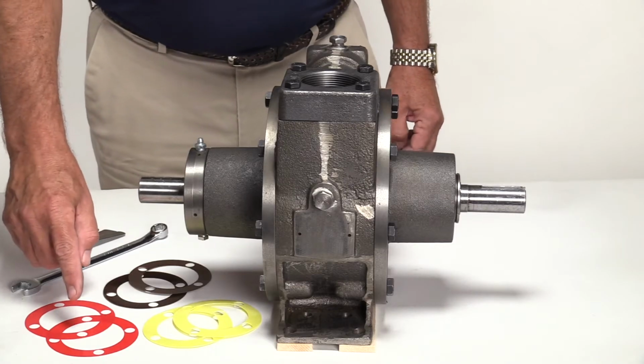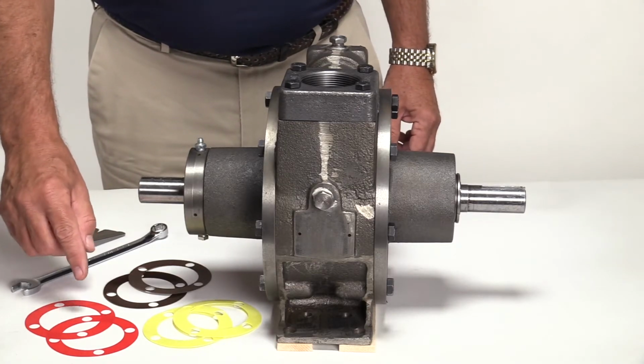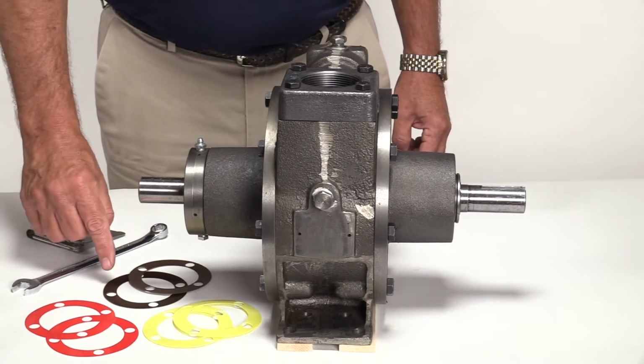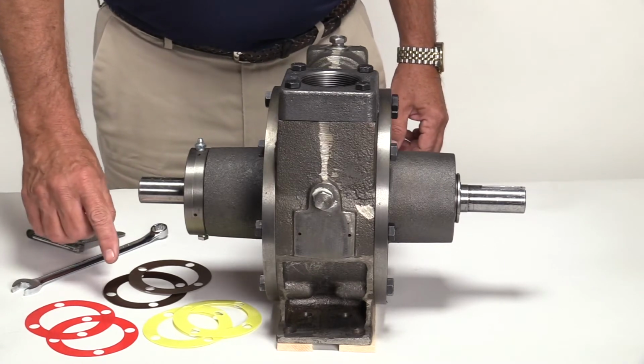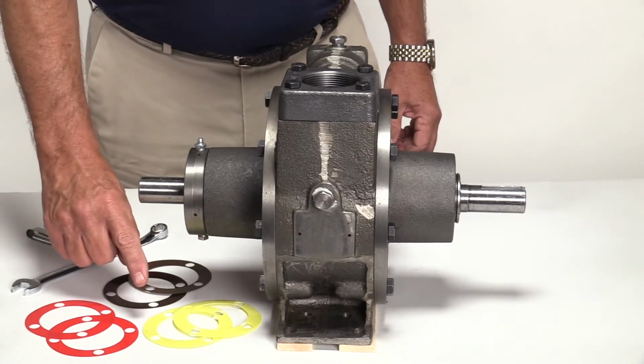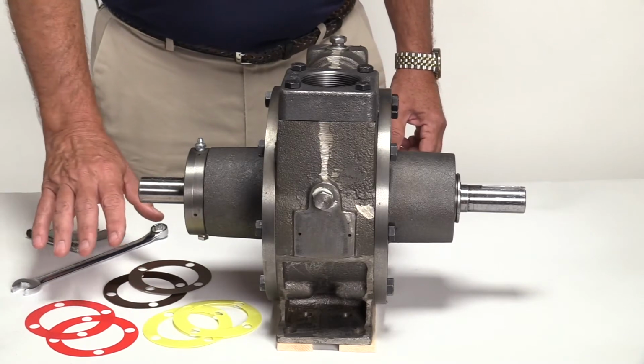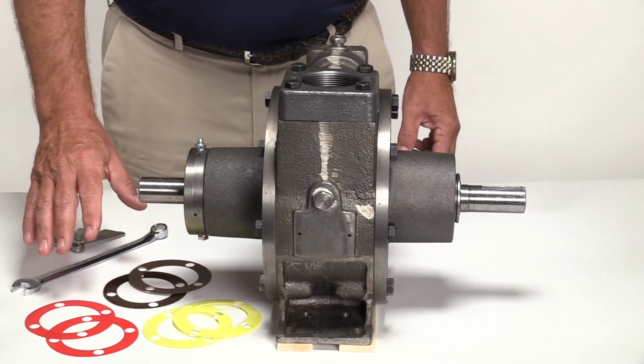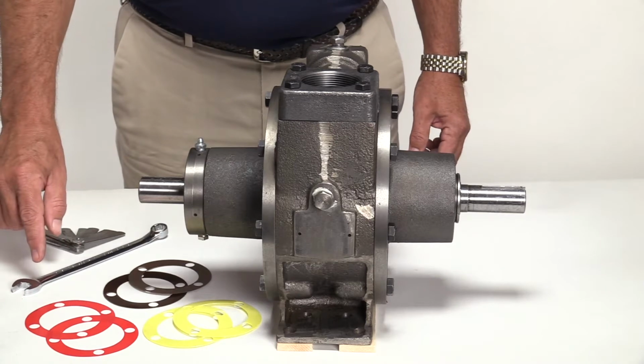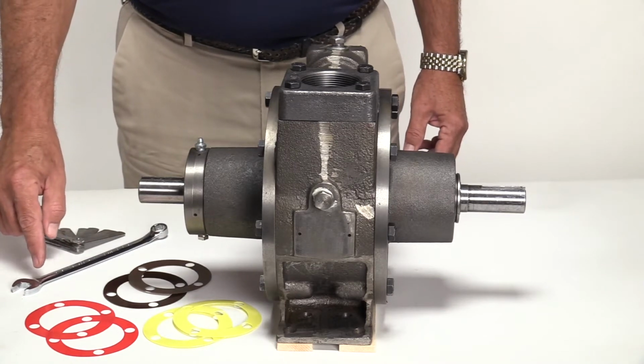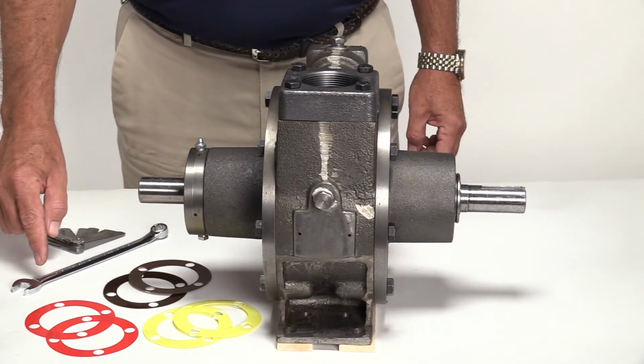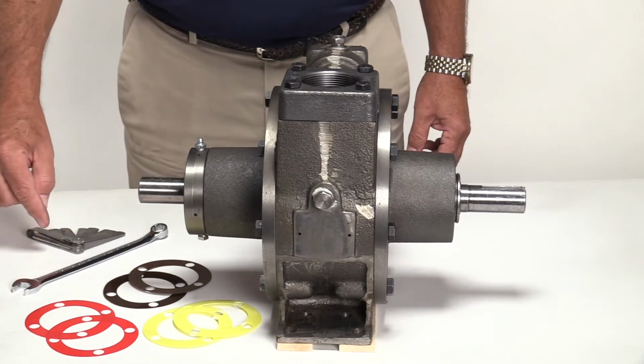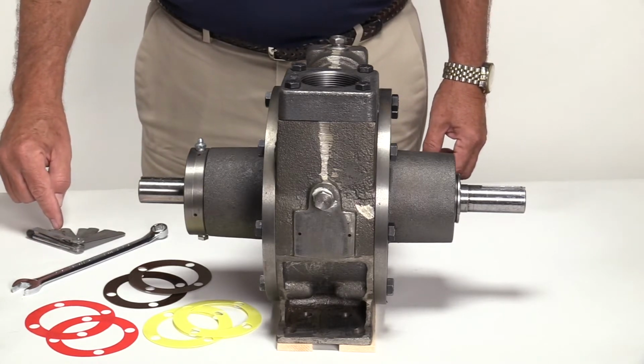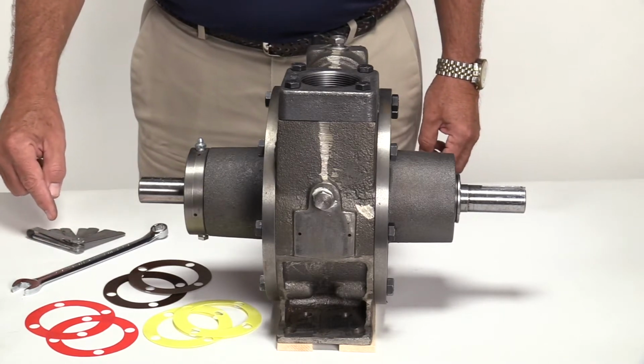Each rebuild kit comes with 8 red .002 shims, 2 brown .010 shims, and 2 yellow .020 shims. A combination of these shims is used to achieve the proper clearance between the rotor and side plate on each side of the pump. You will also need a 9/16 wrench or ratchet and socket and a set of thickness or feeler gauges for checking clearance.